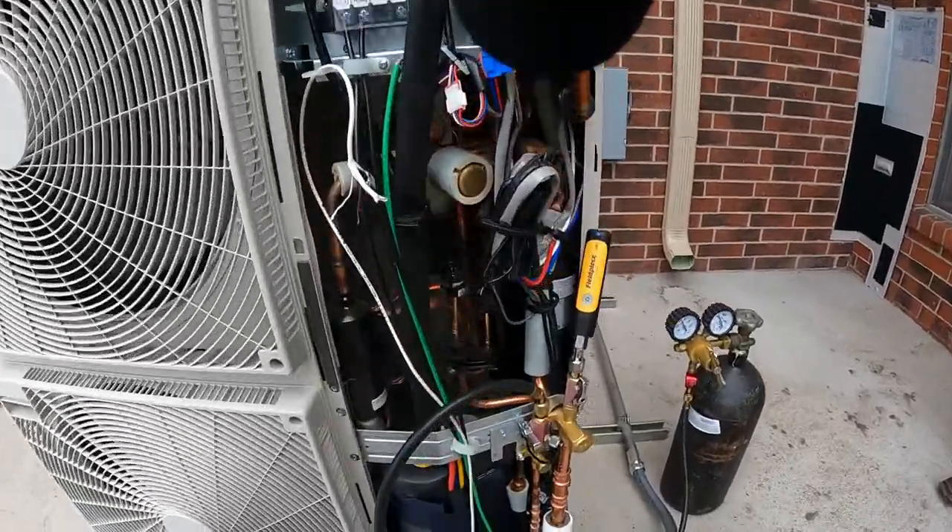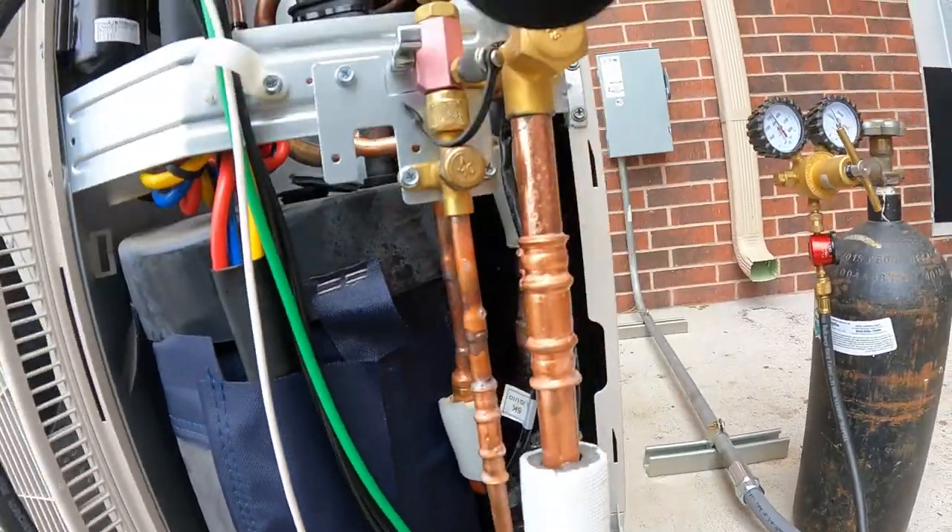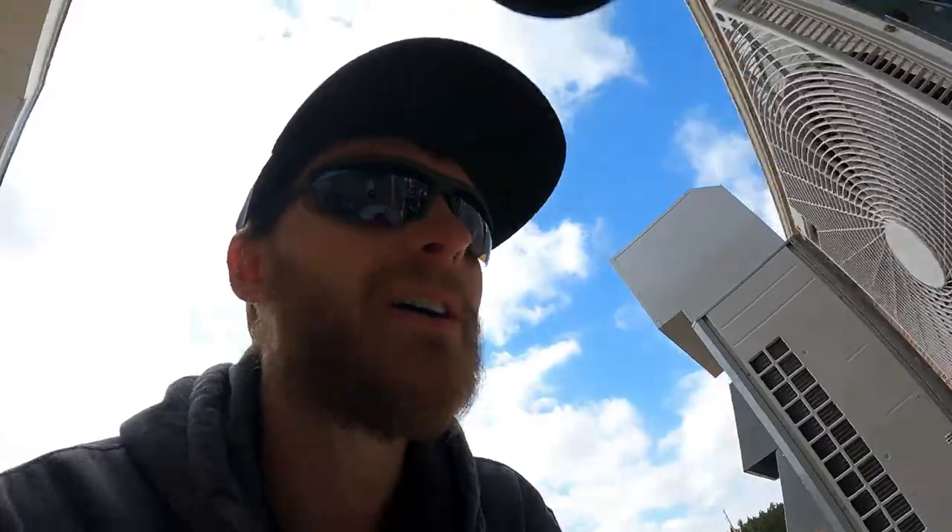There we go. Now we've got everything leak checked. You can tell by the soapiness — I can't get you much closer because of the mic. We got that checked up there, everything indoors is checked too, and they're all good. It's holding pressure right now, so we're going to let that stay as it is. Carry everything back to the attic, and then we will begin brazing over there.